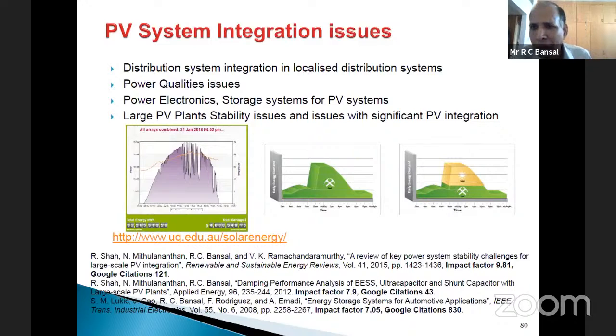Whether you are going to supply almost the whole load, or just consider supplying the essential load. Essential load could be just your lighting loads, maybe some fans, or you want the full luxury, like operating the air conditioning system and the lifts as well. So you have to decide - if you are operating full load, you know how much load you can operate with the battery, it will just last for fewer hours.